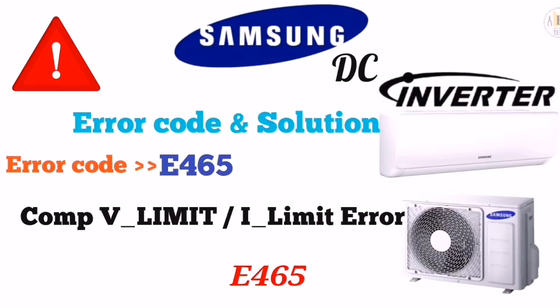Let's see the next error code, E465. When LED 1 is blinking, LED 2 is on and LED 3 is off, it means compressor V-limit error. To solve this issue, you have to follow the steps for the error E464 which I have explained previously, and your unit will be in working condition.